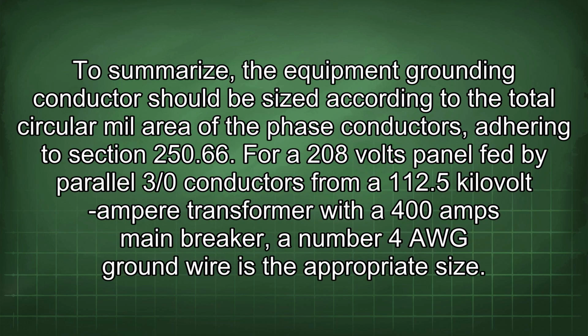To summarize, the equipment grounding conductor should be sized according to the total circular mil area of the phase conductors, adhering to section 250.66. For a 208 volts panel fed by parallel 3/0 conductors from a 112.5 kVA transformer with a 400 amps main breaker, a number 4 AWG ground wire is the appropriate size.